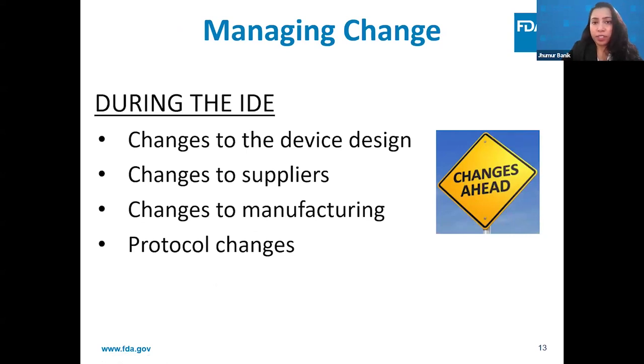There are other things that can happen, understandably so, as product can be developed or enhanced, and there's a broad time between the Q-Sub to IDE development to the actual PMA submission. So sometimes there could be changes to device design over time, the investigational device, changes to the supplier, changes to manufacturing, or even protocol changes. So it is important to make sure that the FDA review team are made aware of these updates early. And because the IDE only has a 30-day review timeline, it is important to make sure that the changes are communicated so those are accounted for, should there be any questions or concerns or additional testing or additional report requests that may be needed in that time.